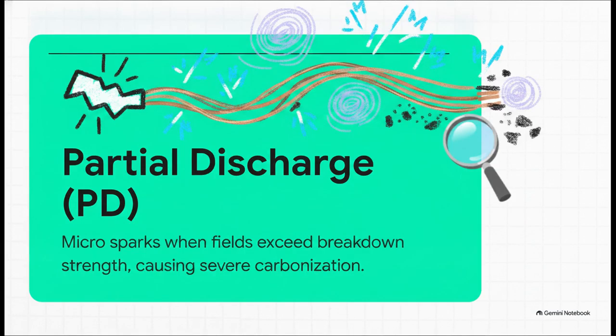Now, let's zero in on that electrical stress for a second, specifically a phenomenon known as partial discharge, or PD. Think of those extreme voltage spikes from the silicon carbide inverter, which can exceed 10 kilovolts per microsecond, by the way, as a high-frequency electrical hammer. This invisible hammer is just constantly smashing away at the first few turns of the copper wire inside the motor. When the local electric field gets a bit too strong, it literally rips electrons right out of the tiny air gaps. This generates ozone and high-energy sparks that viciously eat away at the polymer chains of the insulation, carbonizing it until it just fails.